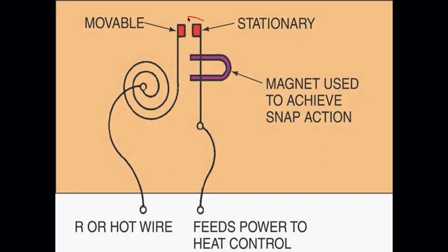Another snap action is this one right here, as this helix begins to expand or contract based on the bimetal element that's in here. Again, bimetal, two dissimilar metals put together. They expand and contract at different rates. Okay, it's going to snap together. This one has a magnet in it to ensure that when this snaps together, there's no bouncing. It's going to snap together and make a good solid connection because of that magnet.